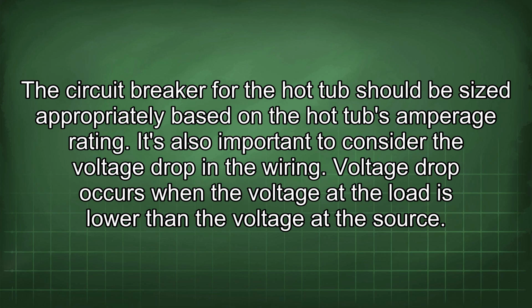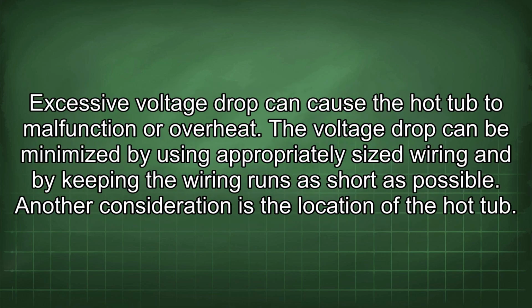Voltage drop occurs when the voltage at the load is lower than the voltage at the source. Excessive voltage drop can cause the hot tub to malfunction or overheat. The voltage drop can be minimized by using appropriately sized wiring and by keeping the wiring runs as short as possible. Another consideration is the location of the hot tub.